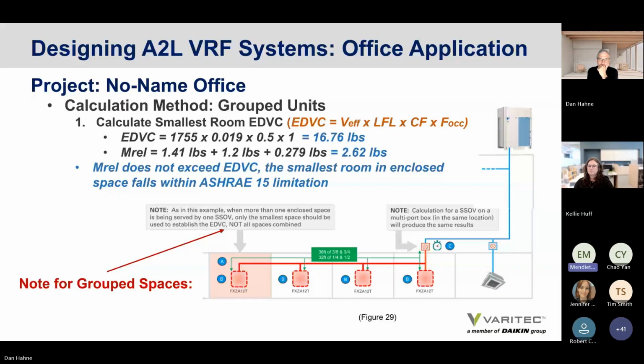Correct. And you're probably referring to outside of ASHRAE. These are UL requirements for enclosed spaces, manufactured components. Is that what you're referring to? Yeah, that's where I'm going with it. So we've seen some of that, where there's mixed guidance right now from different manufacturers, because obviously, number one, it doesn't have a refrigerant sensing device like a fan coil does to basically move air, right? So it's a static device instead. So you've got a problem there where now you have to rely on the RCL charge, not the LFL charge. So there are some issues and concerns there.